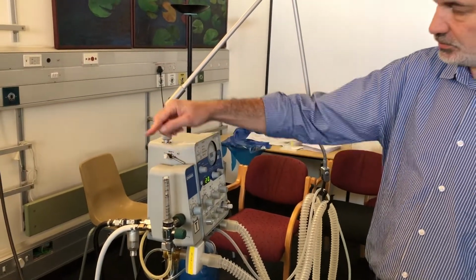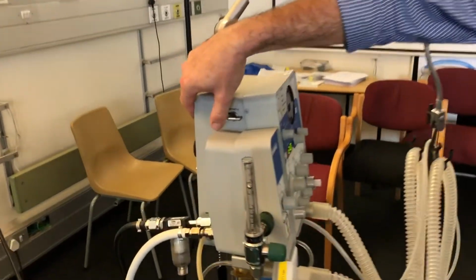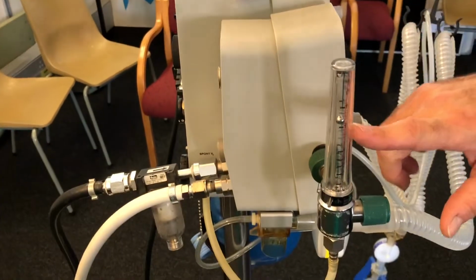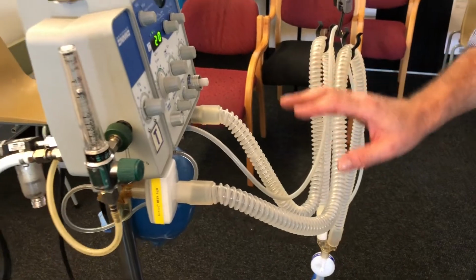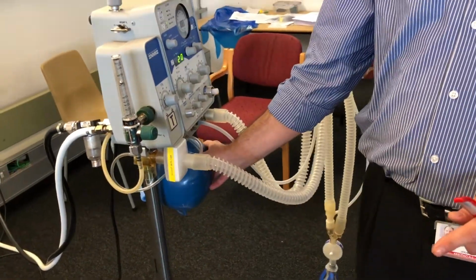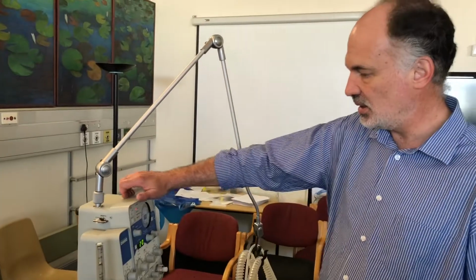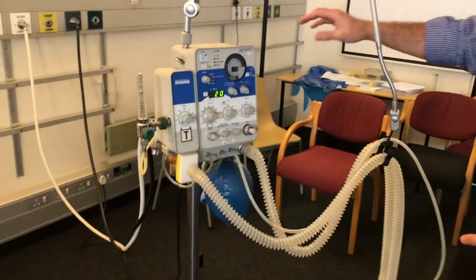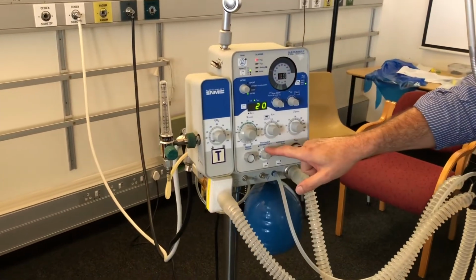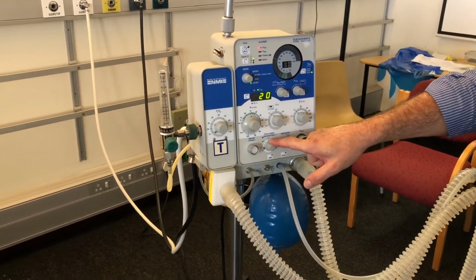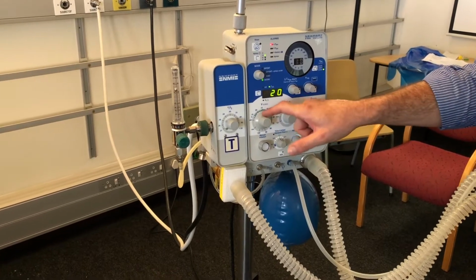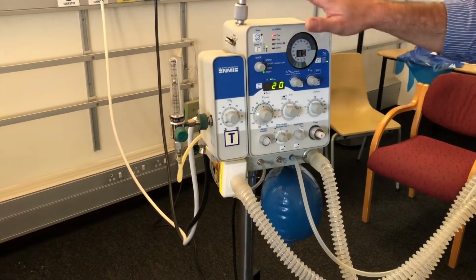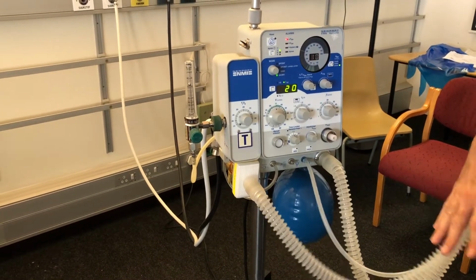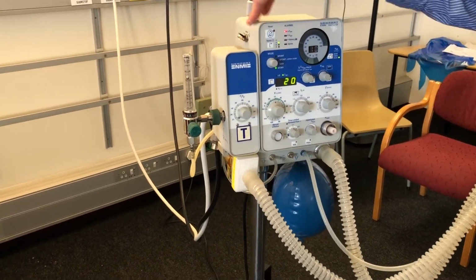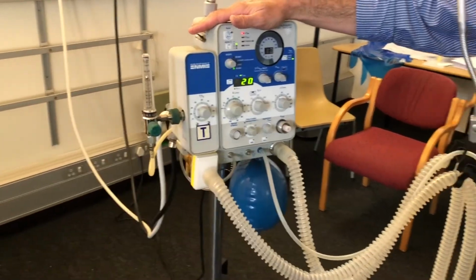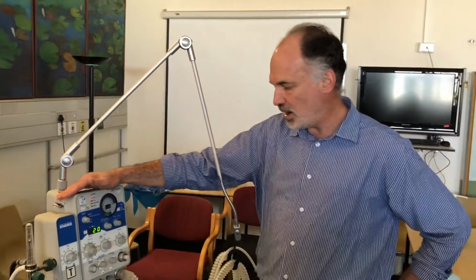Just to remind you though, that all the rotameter and the switch do is determine what the flow rate of gas will be into the circuit and into the reservoir bag for the patient to breathe spontaneously. When we were discussing SIMV and we were discussing time-limited demand flow, I indicated to you that the flow that would be available would be a flow that we'd preset on the machine. In the spontaneous modes, the patient decides the inspiratory flow rate and the machine just makes fresh gas available.